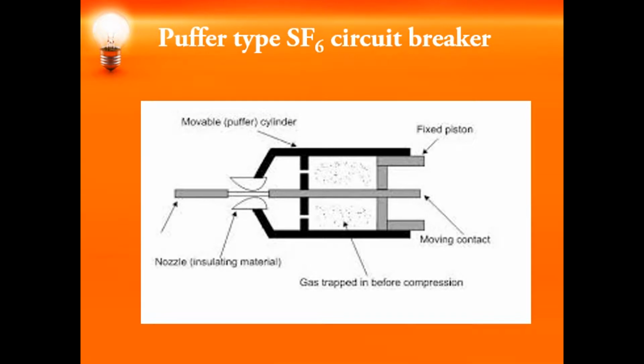Next, coming to the types of circuit breakers. Before looking at the types, what is the arc quenching principle in SF6 circuit breakers? Be it any SF6 circuit breaker, the arc is finally quenched due to regaining of the dielectric strength between the contacts. The regaining of the dielectric strength is achieved mainly by the deionization process. This deionization can be achieved by high pressure, by cooling, and by forced convection and turbulence. Mainly, due to the movement of the electrons and the molecules getting neutralized, the ionized particles get reduced, and the arc is quenched.